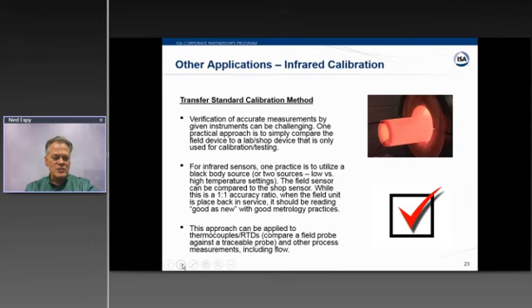There's some other things you can do with this shop sensor to make sure. You might need to send it off every 6 months or something to be checked, but there's some other metrology practices that you can bring into play to make sure you're getting good, consistent results. And this transfer method can be used in other ways besides infrared. You could have a certified thermocouple, so maybe it's a type T thermocouple. Maybe you buy a batch of them, and you can compare any field T thermocouple to your master before you put it in service, or if you're pulling them, you can see if something's really off and do some troubleshooting.